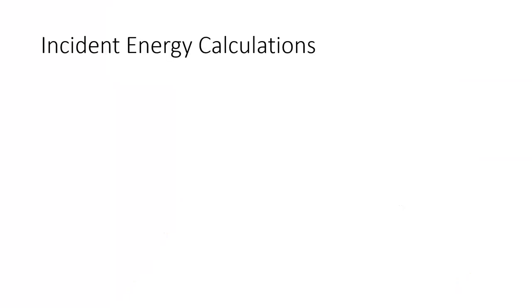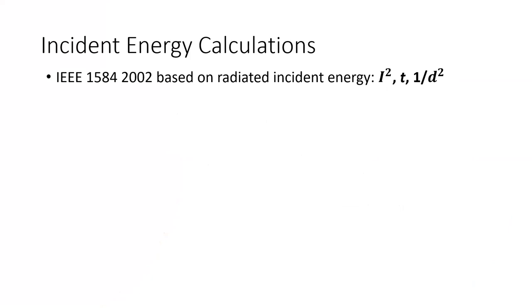Now, I know Kazi looked at this in some detail, but there are just three standards I'd like to go through with regard to incident energy calculations. The first is the old IEEE standard 1584 that we'd used right up until 2018. That was just based on the radiated incident energy, which is proportional to I squared T over D squared. So I squared T is the instantaneous energy, and 1 over D squared is the inverse square law. The further away you get, the energy falls off with the square of that distance.